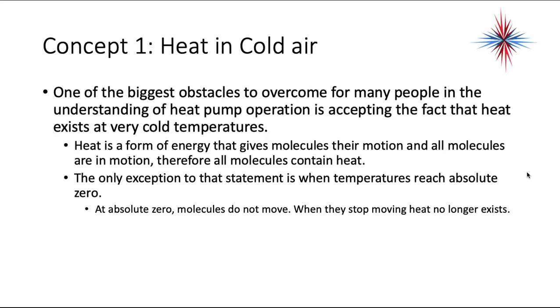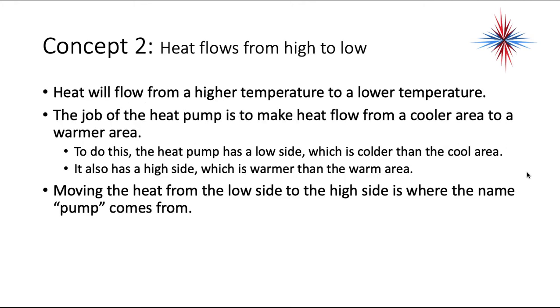So the first concept is heat in cold air. One of the biggest obstacles to overcome for many people in the understanding of heat pump operation is accepting the fact that heat exists at very cold temperatures. You can be outside and feel cold, but there's still heat in that air. Heat is a form of energy that gives molecules their motion, and all molecules are in motion. Therefore, all molecules contain heat. The only exception to that statement is when the temperature reaches absolute zero. At absolute zero, molecules do not move. When they stop moving, heat no longer exists.